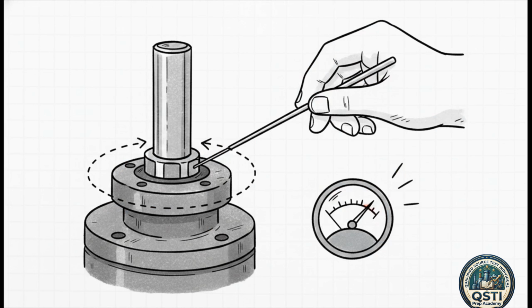Now, for specific equipment like valves, the inspector executes what we can call the sweep technique. They physically place this tiny probe, we're talking no larger than 1/4 inch in outside diameter, exactly at the interface where the valve stem exits the packing gland. Then, they slowly trace the entire circumference, just watching that meter for any spike. If the meter jumps, they stop right there and sample that exact spot for twice the instrument's response time, just to ensure they capture the absolute maximum concentration. It is incredibly meticulous work.